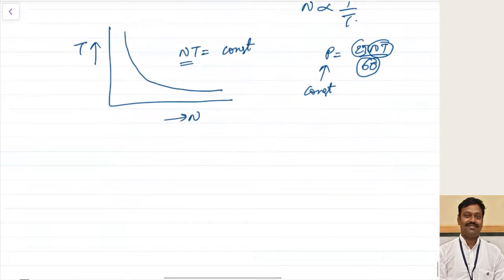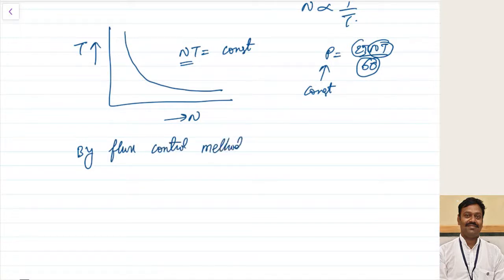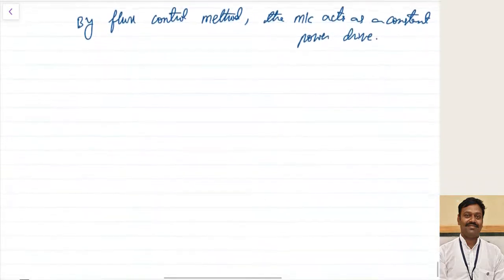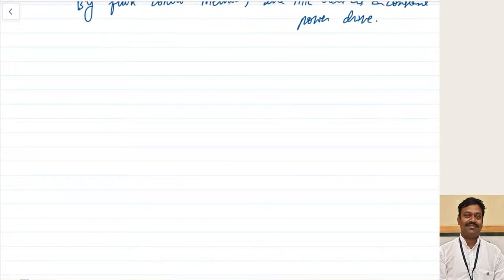Since N×T is constant and power P equals 2πNT divided by 60, the power will be constant. Therefore, by the flux control method, the machine acts as a constant power drive. We have discussed constant power drive in the previous lecture, lecture number 16.